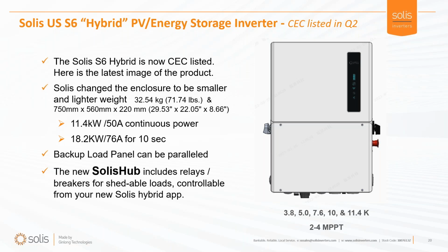What's exciting about these transformerless inverters is their capability to handle surge. You can see we can put out 47.5, almost 50 amps continuous on these inverters, but we can also put out 76 amps for 10 seconds to start up those large air conditioner units. We're actually building up towards 100 amp. My colleagues overseas have difficulty believing that we would have some sort of 5-ton air conditioner in a home, but indeed it happens, so these hybrids really have to be quite capable when it comes to surge.